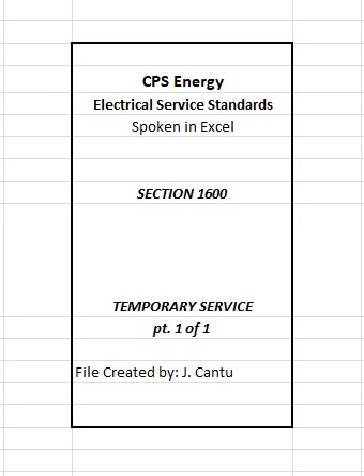1604.2 Service entrance conductors, service raceway. Customer shall provide and install the temporary service entrance conductors and service raceway from CPS Energy service drop conductors to metering equipment, refer to definition of service entrance conductors. Customer shall be responsible for installing conductors in accordance with 1 through 3, below.